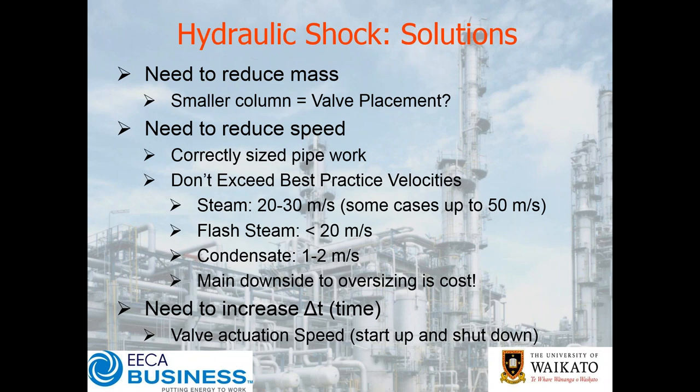The other way to get our force number down is to increase our delta T — in other words, increasing the time by slowing down the valve actuation speed. It's very important on startup and shutdown: do we just shut things off in a hurry, or do we let things cool down and slowly wind down? It's very important with steam and condensate systems to be careful in setting and tuning your ramp rates both on startup and shutdown.